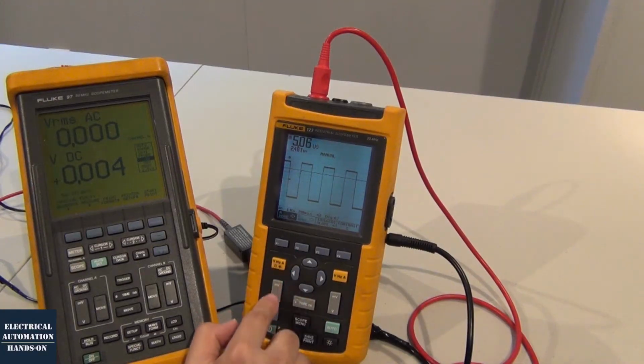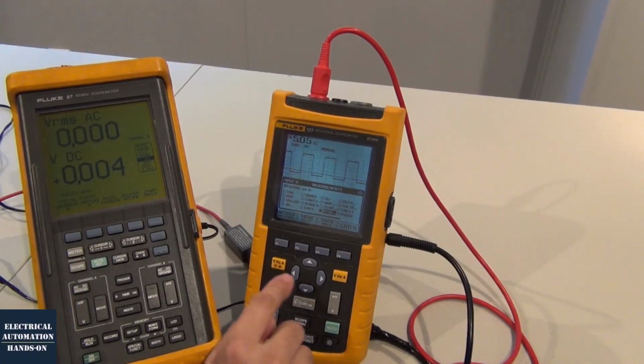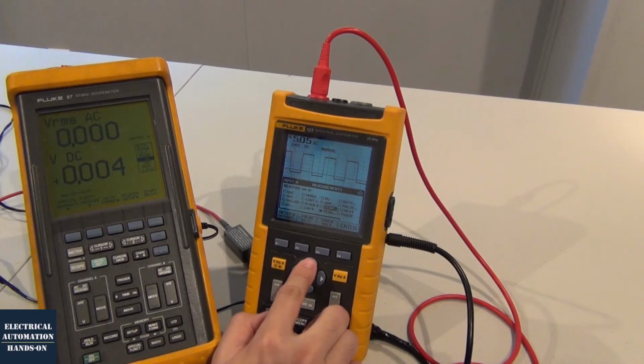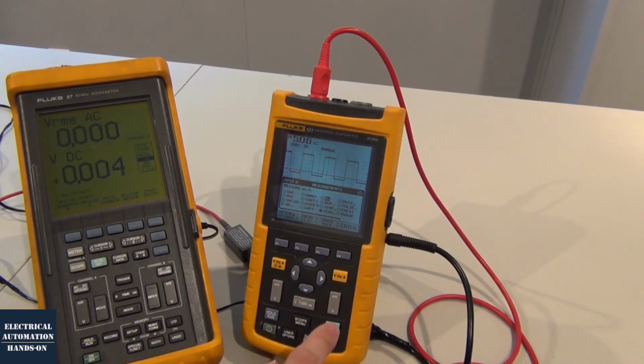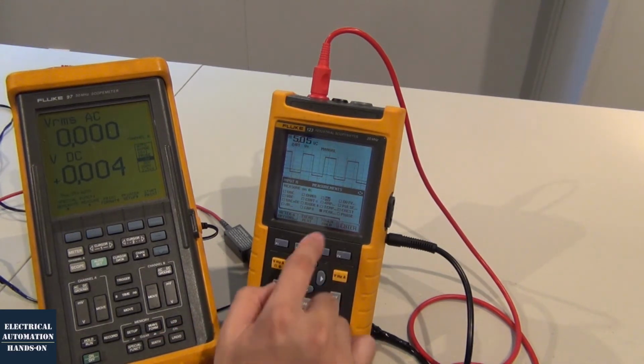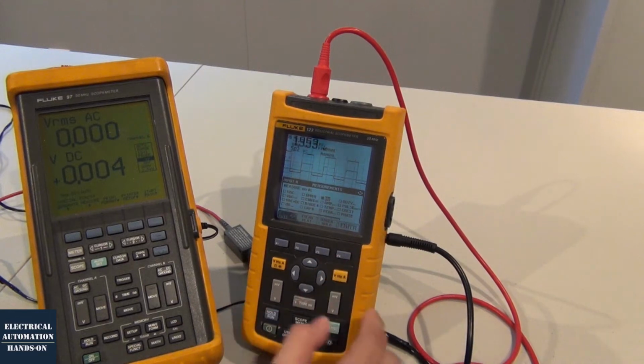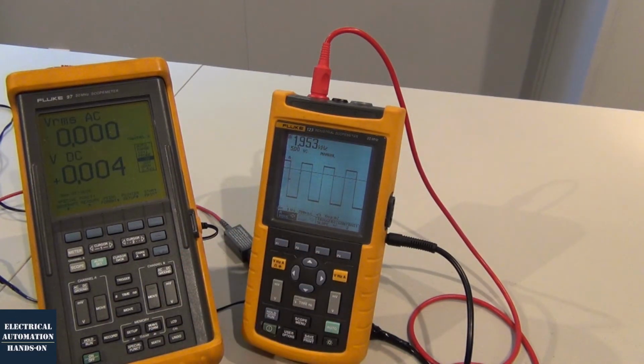In the meantime, we can also click this channel button and select the Hertz. And because the signal coming from this generator is 1.95 kHz, after I select this Hertz, we will see it measures 1.95. It measures the frequency.